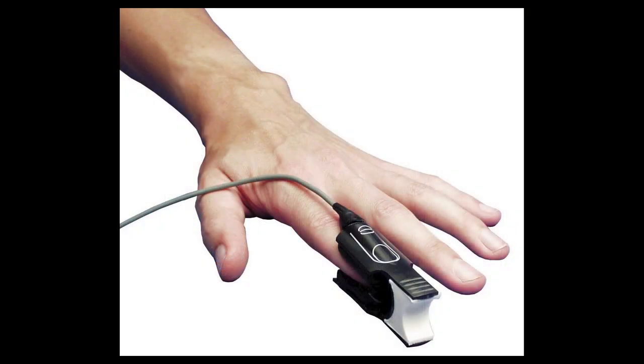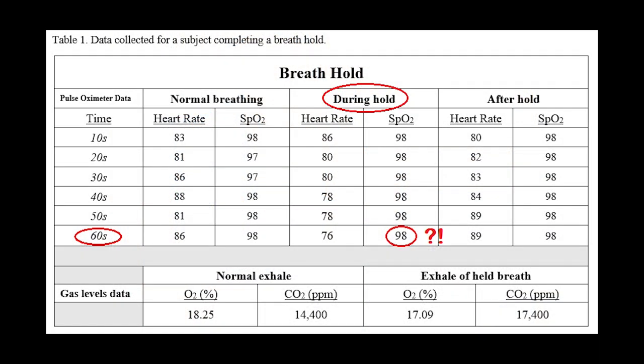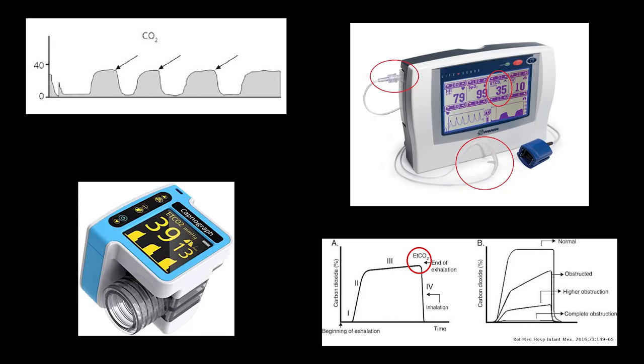If there are any discrepancies with the readings, it's almost always the sensor or the cabling. SpO2 is the standard for patient monitoring, but it does have some pretty big drawbacks — like a huge delay in physiological changes, and it doesn't show any data that diagnoses the second half of the circulatory system, cellular metabolism, venous blood, and CO2 diffusion in the lungs. For these shortcomings, we have capnography and end-tidal CO2 monitoring.